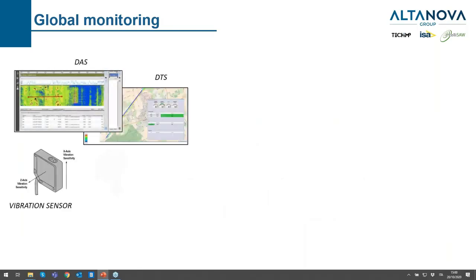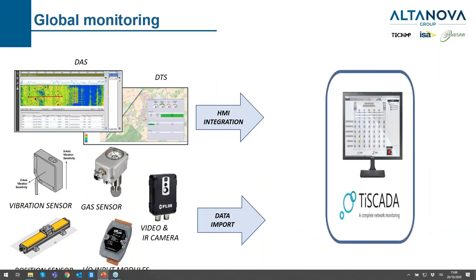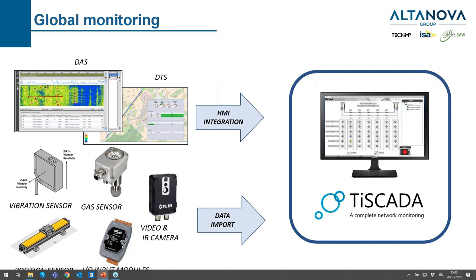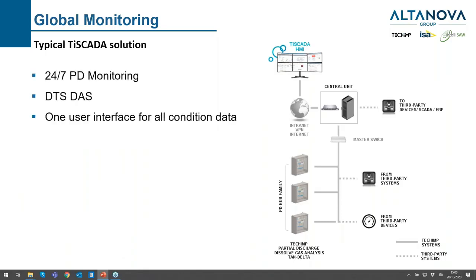Here we have an example of the HV cable global monitoring: we have DAS, DTS, vibration sensors, gas sensors, video camera, infrared, position sensors, and input modules. We can make both HMI integration and data import. Everything is in our TiSCADA system. A typical example with global monitoring provides 24/7 PD monitoring, DTS and DAS — one user interface for all condition data on a web-based platform, so you can access it from your laptop by connecting to the same network.